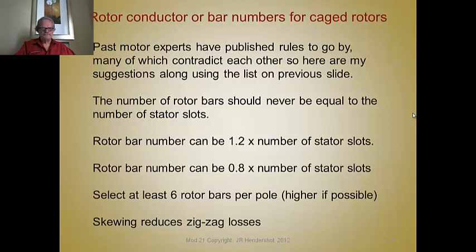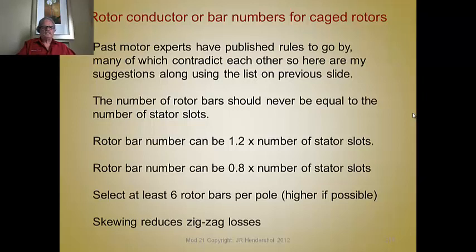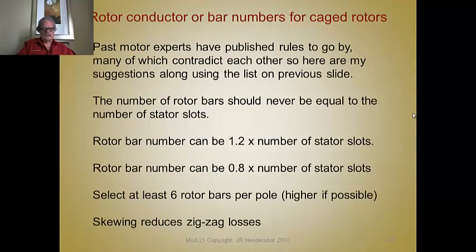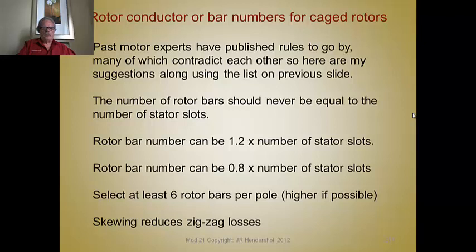We have to select the number of rotor bars — that's important. There are lots of rules and guidelines for that. Most of the critical ones have been for single-phase machines, which can have resonance problems and get stuck and won't start with certain inertia loads. But with three-phase polyphase machines that's not as big a problem. One guideline is that the rotor bar number should be about 1.2 times the number of stator slots, or 0.8 times the number of stator slots — it can never be the same. To adequately establish poles in the rotor that will generate sinusoidal voltages, you need a certain number of bars.